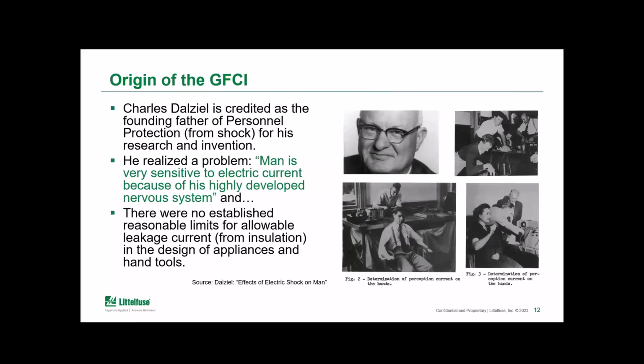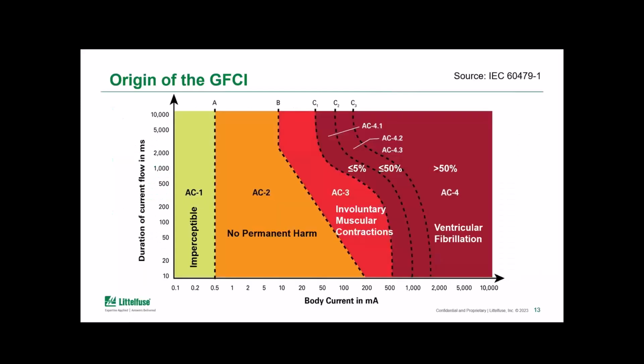The realization that these shocks and fatalities were caused by ground faults, even on common circuits, led him to help participate in the creation of the first GFCIs in the early 60s. His research is what forms the basis of some of the IEC standards on shock protection. This graph showcases data from IEC 60479-1, which shows the effect that both the body current as well as the duration of that current flow will have on the severity of the shock. We'll come back to this chart on future slides, but I just wanted to introduce it here.